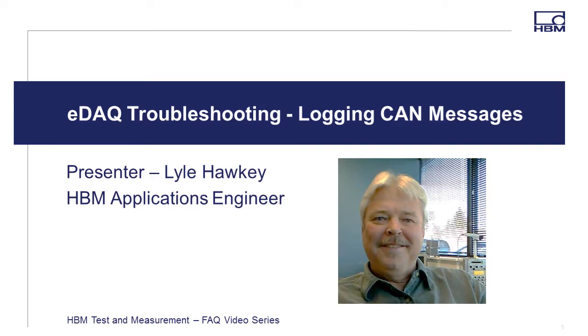Viewing live CAN messages is a good method to confirm that the eDAQ is indeed receiving CAN data. Logging CAN data is a good way to troubleshoot CAN issues when the eDAQ is not collecting good CAN data. This video does not address CAN database design or database troubleshooting. This discussion is about the physical CAN connection between eDAQ and CAN controller.